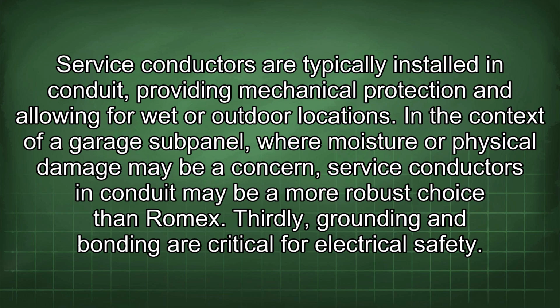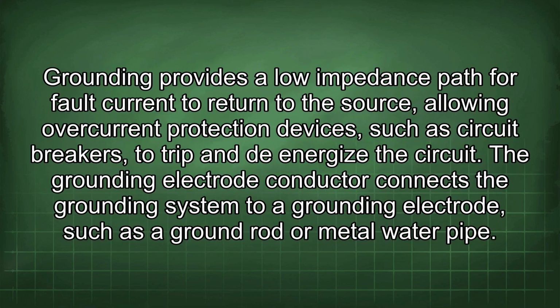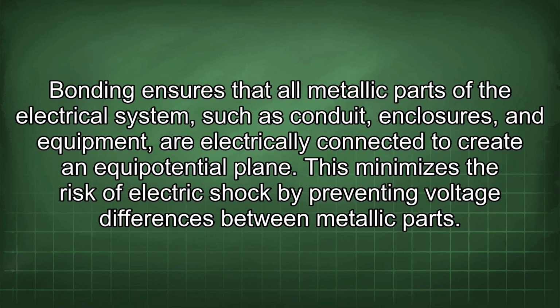Thirdly, grounding and bonding are critical for electrical safety. Grounding provides a low impedance path for fault current to return to the source, allowing overcurrent protection devices such as circuit breakers to trip and de-energize the circuit. The grounding electrode conductor connects the grounding system to a grounding electrode, such as a ground rod or metal water pipe. Bonding ensures that all metallic parts of the electrical system, such as conduit, enclosures, and equipment, are electrically connected to create an equipotential plane. This minimizes the risk of electric shock by preventing voltage differences between metallic parts.